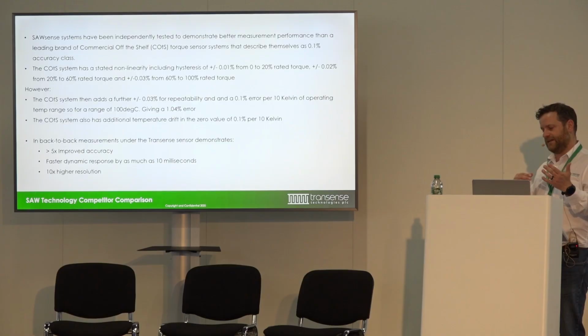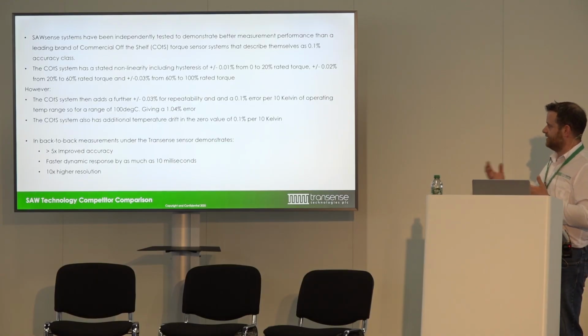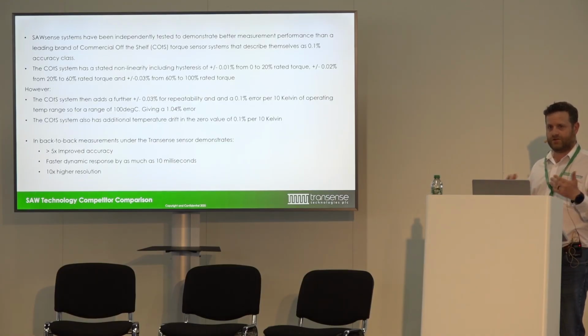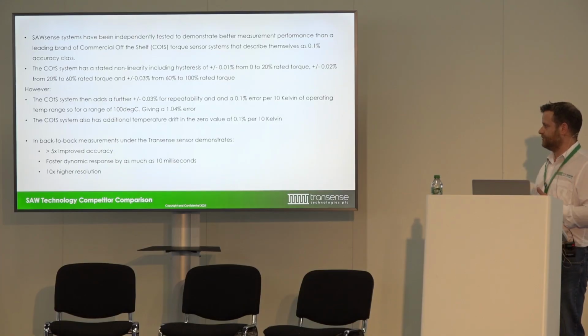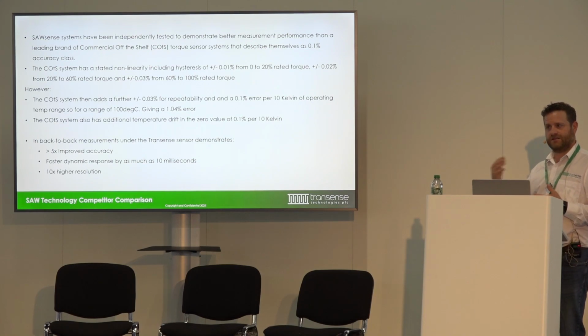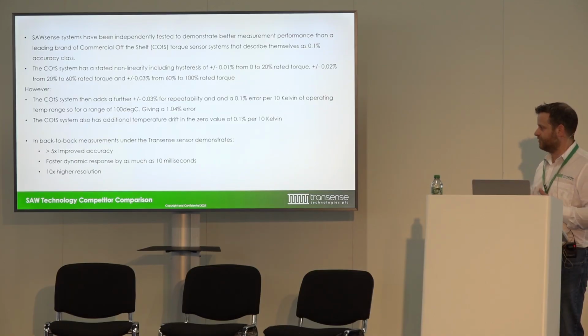So even though the headline figure is 5 times the quoted figure from the off-the-shelf system, we're actually getting 5 times better accuracy, in the other direction from the SAW system, a much faster dynamic response - a 10 millisecond faster measurement coming out of the system compared to a conventional sensor.